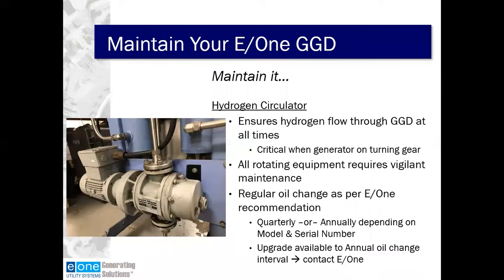So let's talk a little bit about the hydrogen circulator. It's a very critical piece of equipment to the generator gas dryer, in that it's always ensuring that hydrogen flow. And again, on turning gear, it's very critical that we're doing that to maintain the dew points during that critical time of the generator. But with all rotating pieces of equipment, it requires vigilant maintenance. So it's important to be up to date on the maintenance of your hydrogen circulator to ensure the performance of the dryer and the maintenance of the dew point in your generator. And the oil change is the most critical element of that.